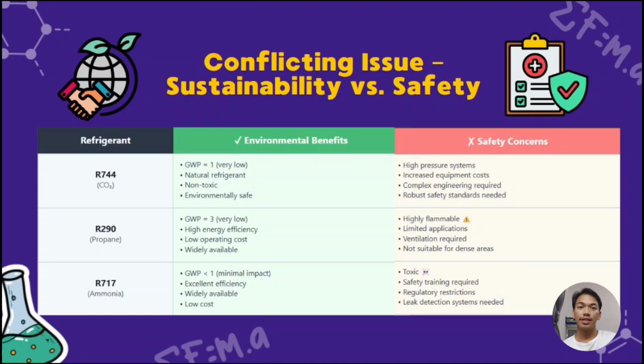R290 propane is incredibly energy efficient and has very low global warming impact. But there's a critical problem: it is highly flammable. This makes it unsuitable for many applications, especially in densely populated areas or spaces with poor ventilation. And R717 ammonia has excellent efficiency and environmental profile, but it is very toxic and could pose serious health risks, requiring extensive safety training, leak detection systems, and strict regulatory compliance.